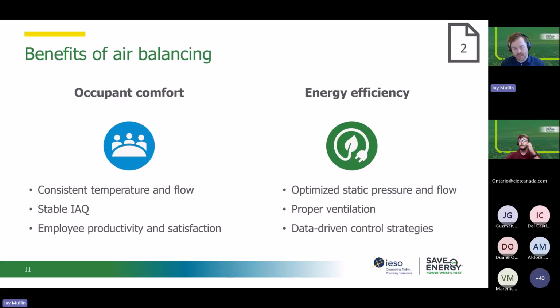You have more consistent temperatures, better employee satisfaction, better indoor air quality. It can improve energy efficiency. So balancing this out can prevent over-ventilation or under-ventilation, which wastes heating and cooling energy. It can allow fans and equipment to operate at their intended static pressure and speed, reducing electrical demand. Because if you have negative pressure in your facility, the exhaust fans now have a greater static pressure that they're kind of fighting against. So that's going to increase energy consumption.